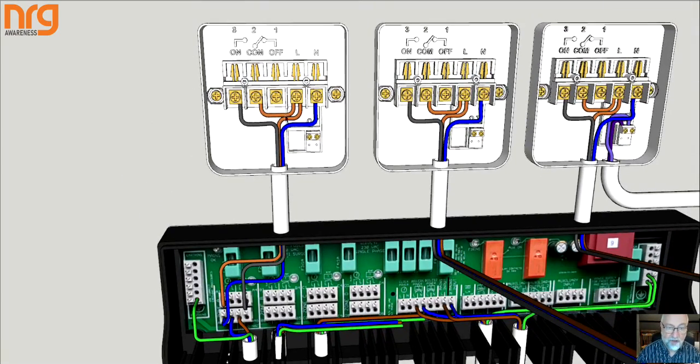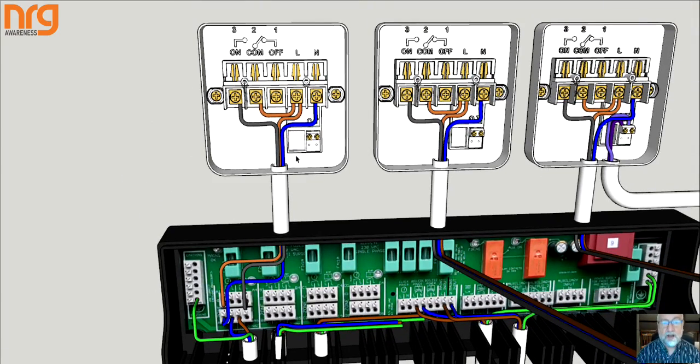And in the open term units, we have need for a live, which is coming up on the brown wire from the fuse. It links as well over onto the common of the output relay. And then from the normally open of the output relay, it goes back down to the 4th terminal. So look, you can see here's the perfect circuit up into the common.